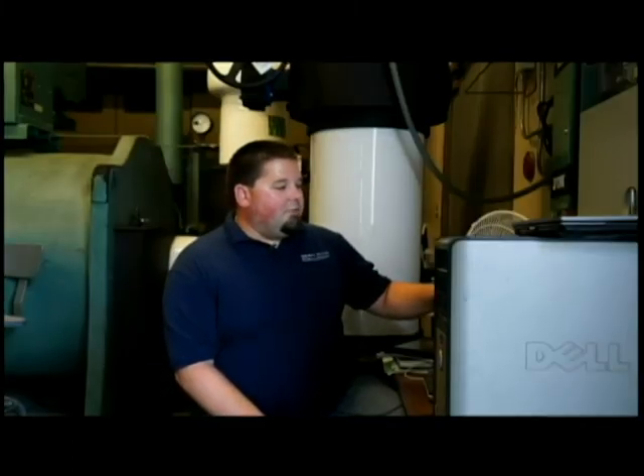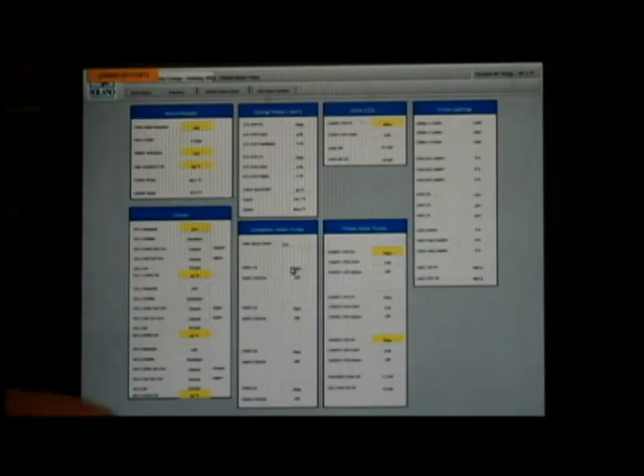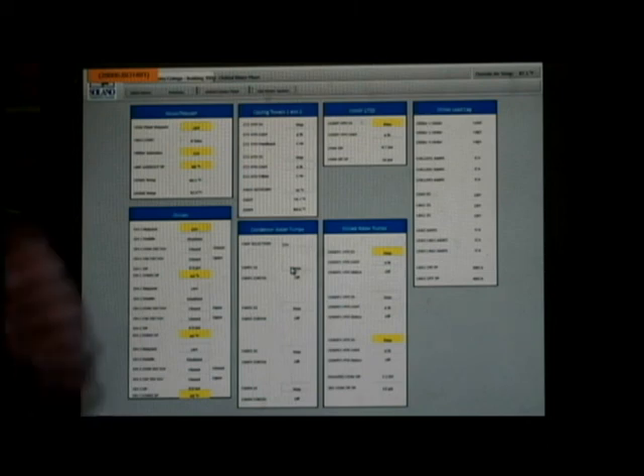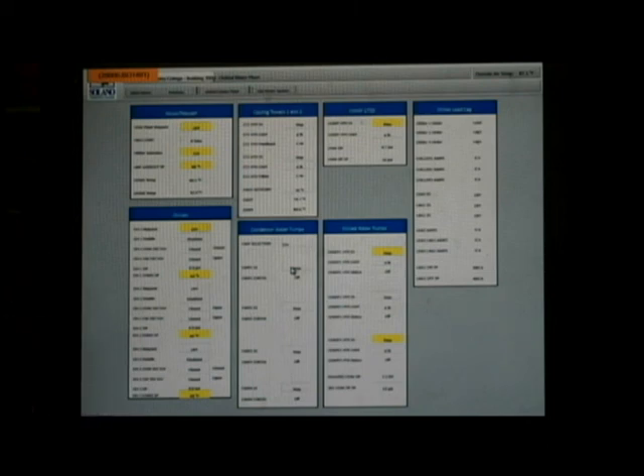Down here is where we actually tell the chillers what temperature we would like to achieve out of them. Each chiller has its own onboard controller. It maintains all of its own functions internally. So basically we give it a green light and a set point, and it is up to that chiller and its onboard controls to get us the desired temperature coming out of it.